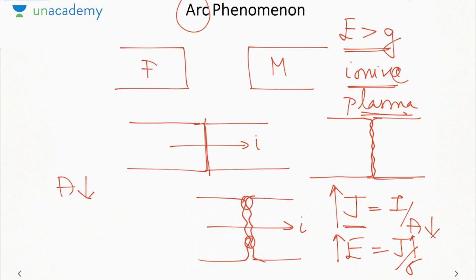Now the whole purpose of the circuit breaker is lost if arc persists. Why? Because the purpose of the circuit breaker was to open the circuit so that no current flows. But now the current still flows, but through the air. Hence we need to extinguish this arc. It is called extinction, so that the circuit breaker is finally opened and there is no current flowing between the plates of the circuit breaker.